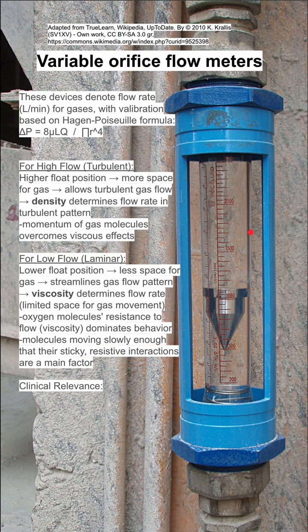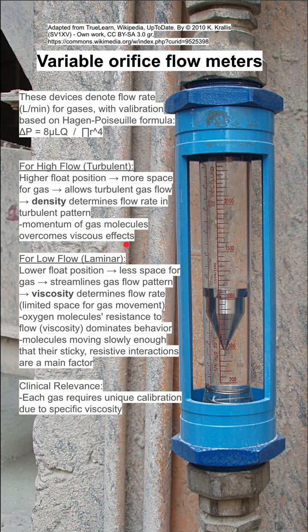Think of this as friction when the flow is low. When the flow is higher and the bobbin is in a higher position, there is more space for the gas to go around, allowing for turbulent gas flow. In this case, density is the primary gas characteristic that determines the flow rate, and the momentum of the gas molecules helps them overcome the viscous effects.